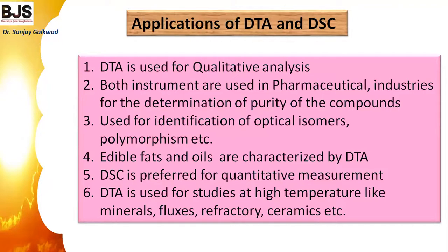Applications of DTA and DSC include: qualitative analysis; determination of purity of compounds in pharmaceutical industries; identification of optical isomers and polymorphism; and characterization of edible fats and oils. DSC is preferred for quantitative measurements requiring precise heat quantities. DTA is used for studies at high temperatures, such as mineral fluxes and refractory ceramics, where temperatures may reach from 1500 up to 3000 degrees Celsius — temperatures unsuitable for TGA or DSC.